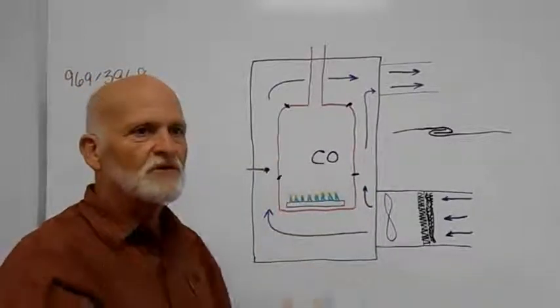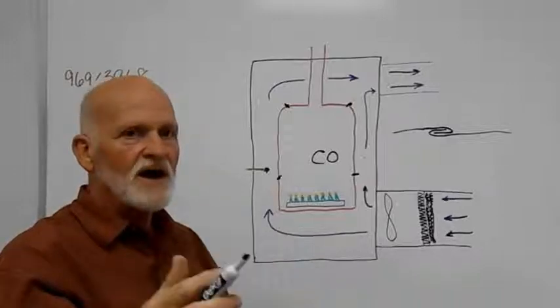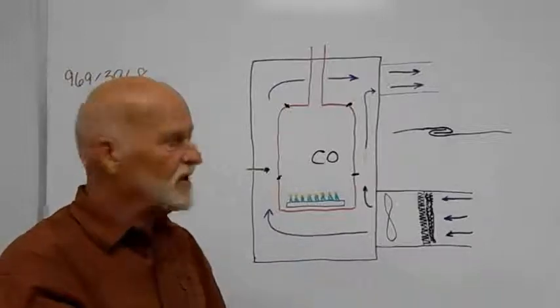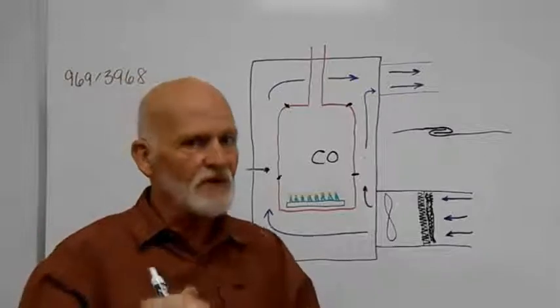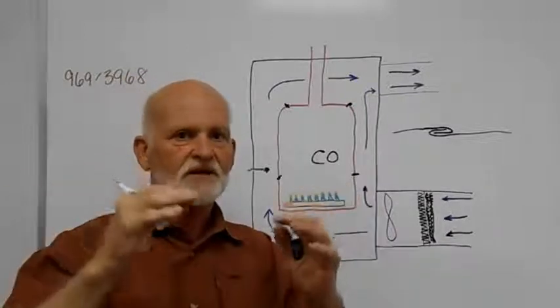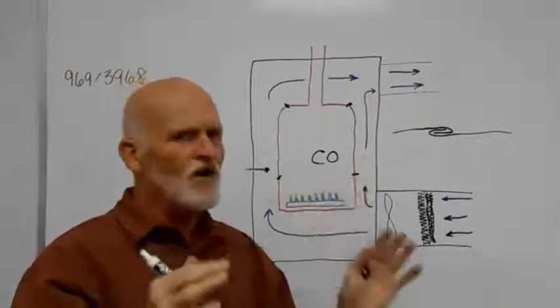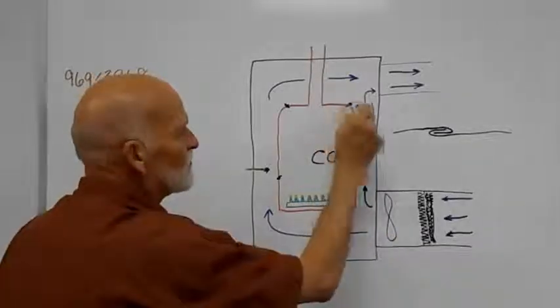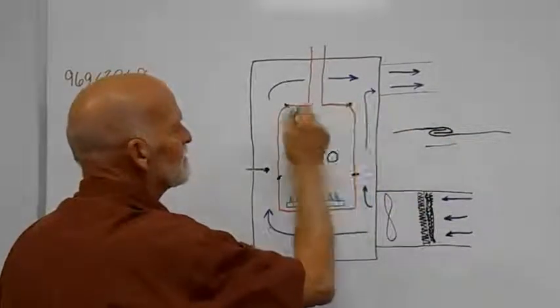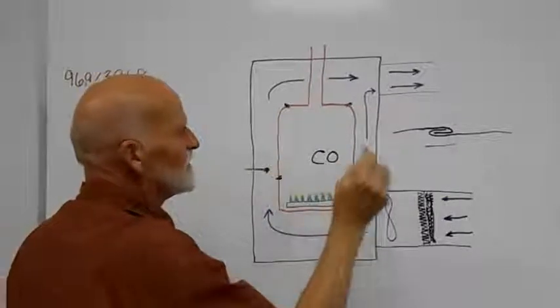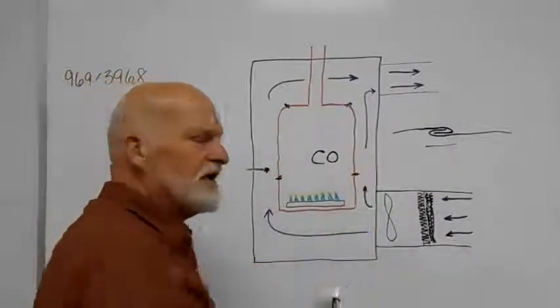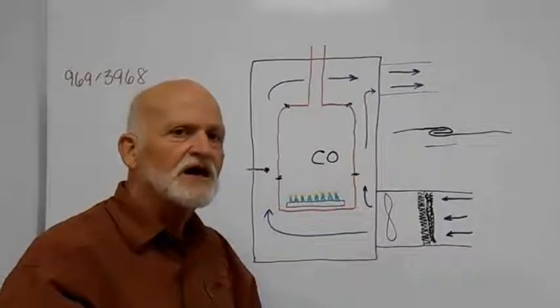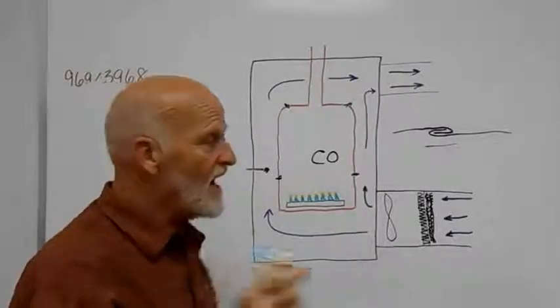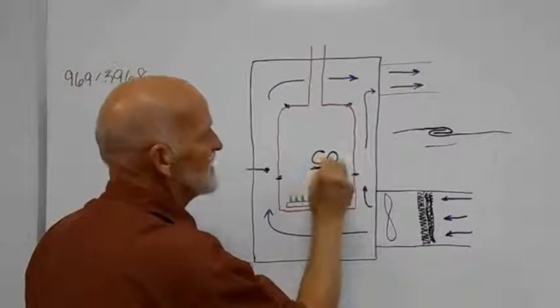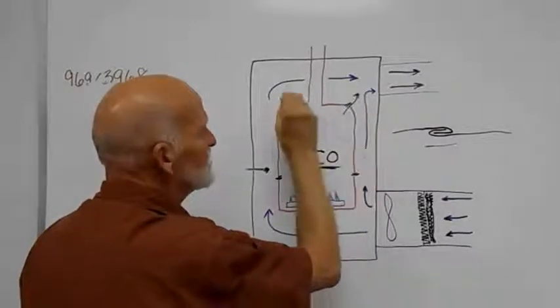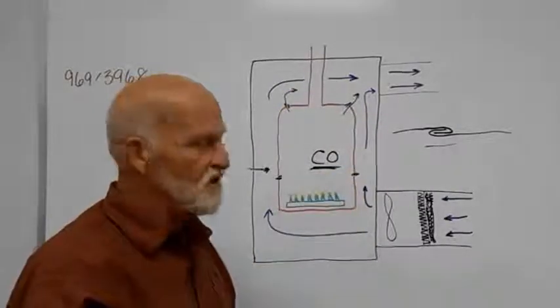You'll never know it. The furnace will go off, it'll cool down, it'll come back on when it gets cool enough and run again. This constant overfiring will continue to expand and contract that heat exchanger far more than it was designed to do. And where they put these seams in, which could be several of them, those seams will expand and contract more than they're designed, and you get little tiny fracture cracks in there. That will allow the carbon monoxide to go out and mix with your airflow that you're breathing.